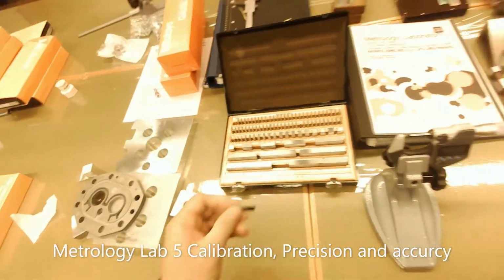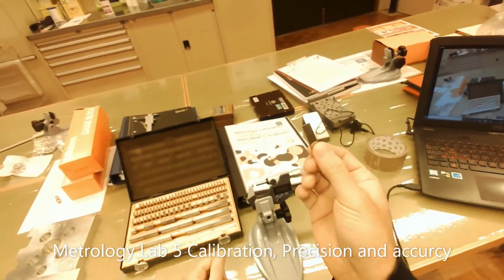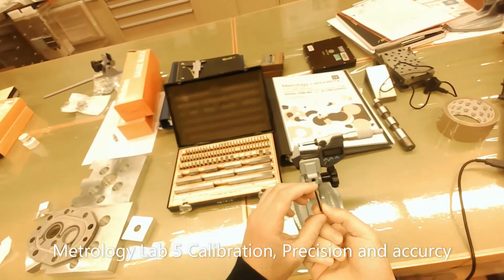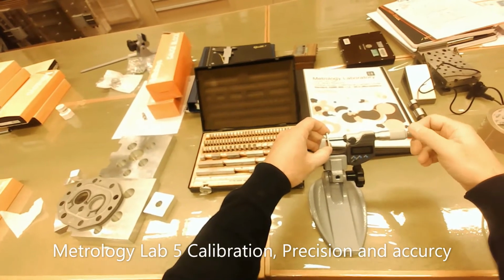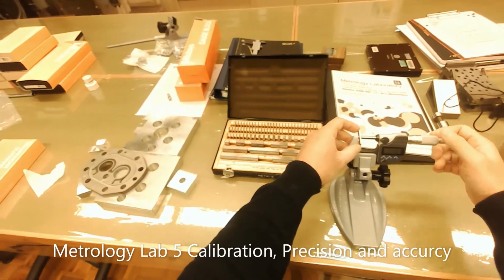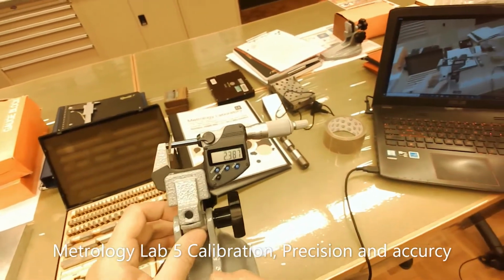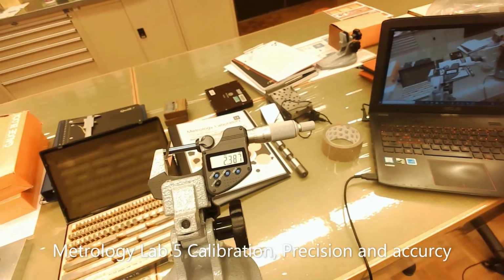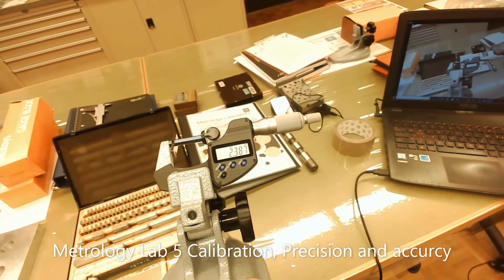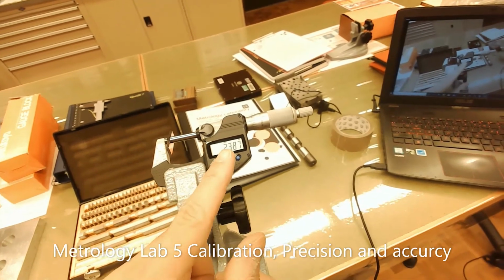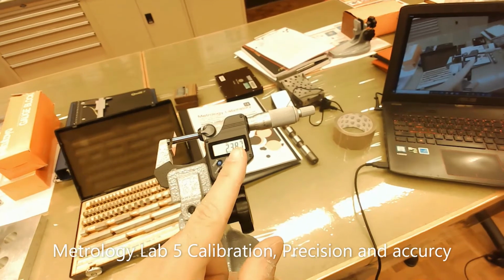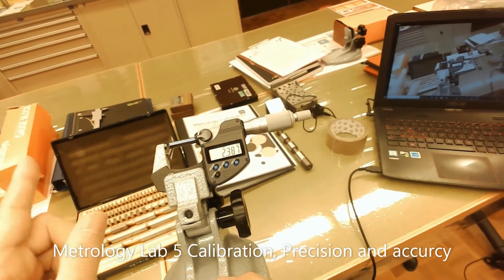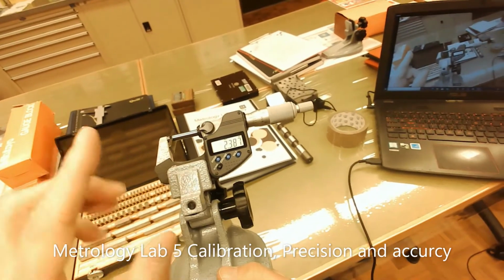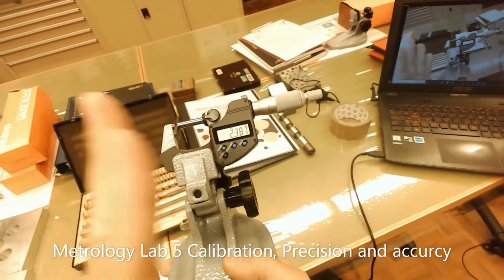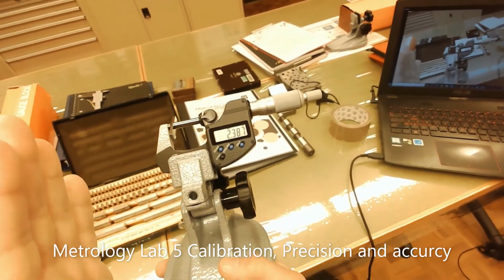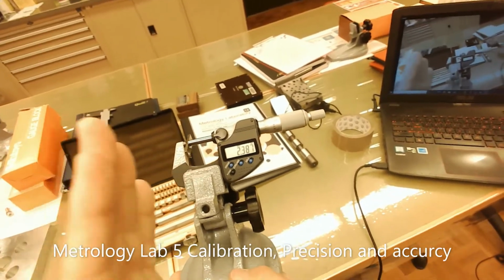This systematic error means I need to record this error and always add or subtract its value. Now the other part I have here is a single block, which should have 2.39 millimeters thickness. I'm going to put this one in and check the reading. The reading I have here is 2.387. I should have 2.39. So now I have a 0.003 error in the reading. In the previous one I had 0.001. So the range of the error for this device is anything from 3 thousandths of a millimeter down to 1 thousandth of a millimeter.